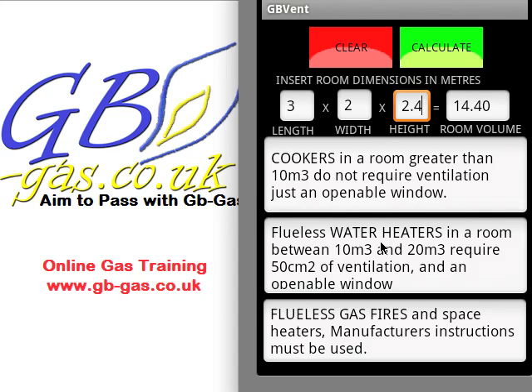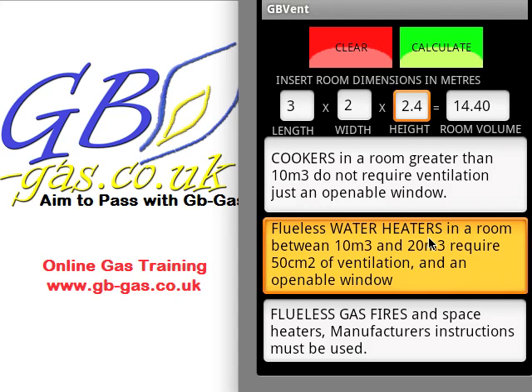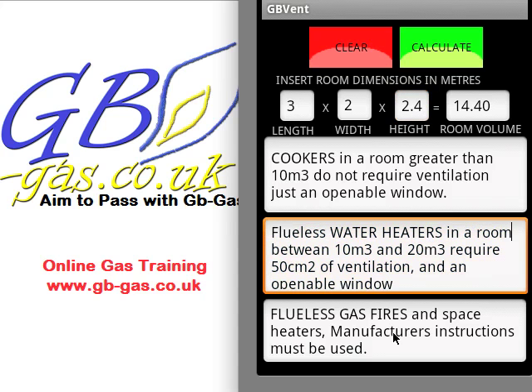For flueless water heaters in this room, we would need a vent of 50 cm² and an openable window. These screens do move for additional text information, and the one at the bottom is for flueless gas fires. Modern flueless gas fires do not comply with any calculation method — we really need to look at the manufacturer's instructions. For most modern flueless gas fires there is a minimum room volume and a ventilation requirement that goes with it, and this must be adhered to.